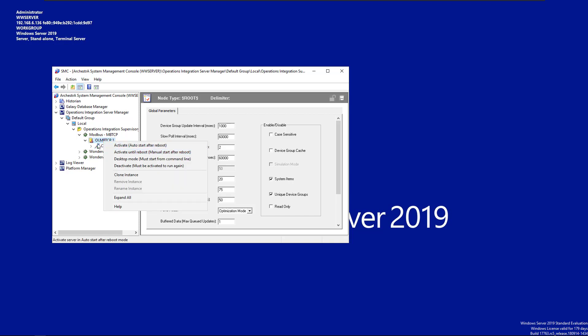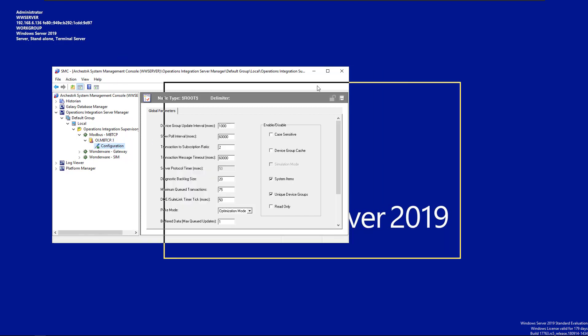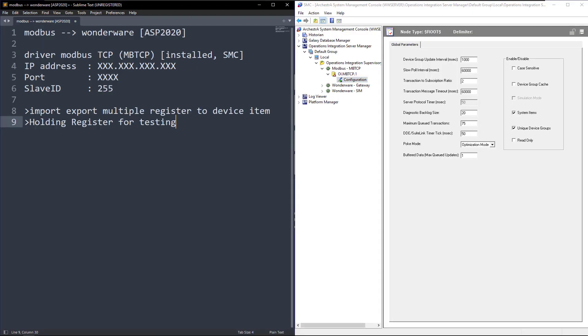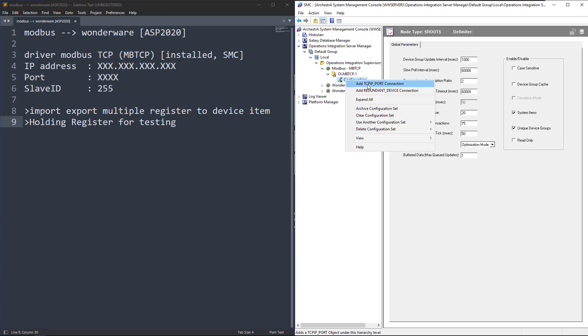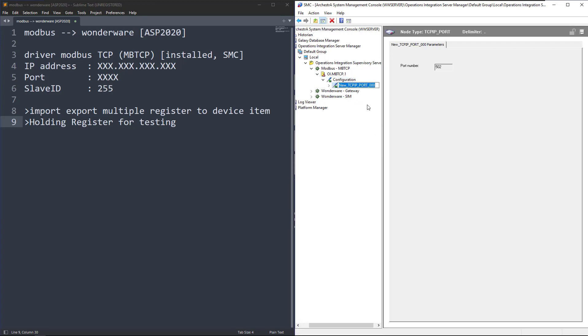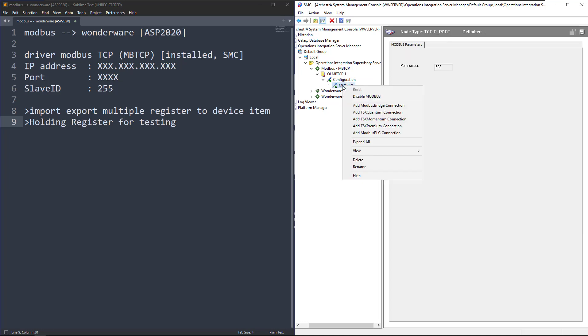We have to start it after we configure the device. Make sure the Modbus TCP driver is installed in the system and visible in the System Management Console. We're going to use the IP address for communication, the port of the Modbus device, and the slave ID — we'll use 255. Now I'm going to right-click and add a TCP port connection; I'll name it 'modbus'.